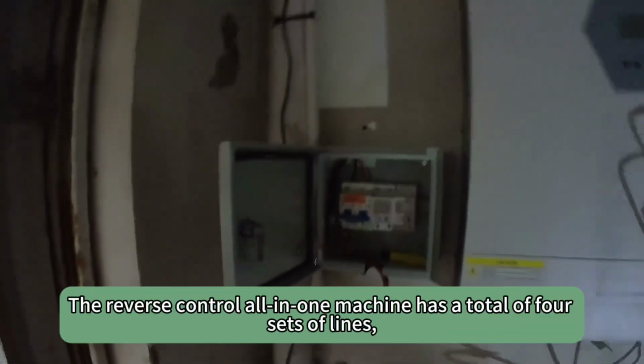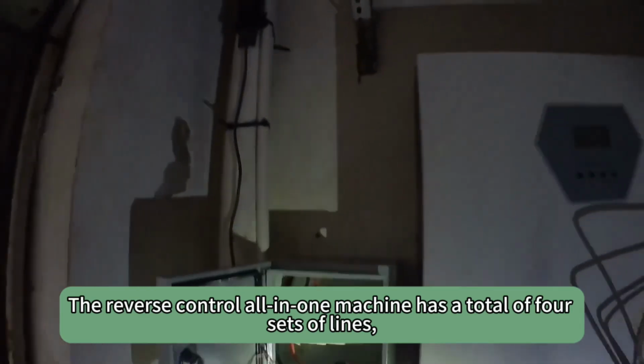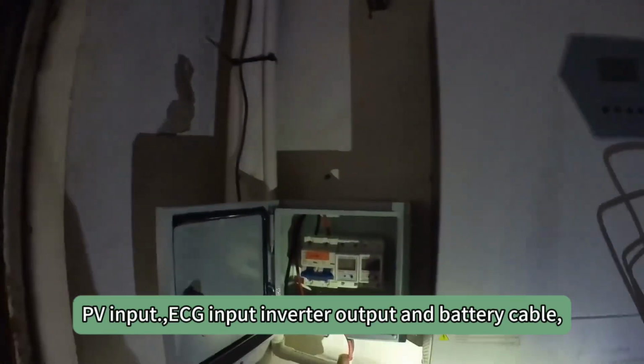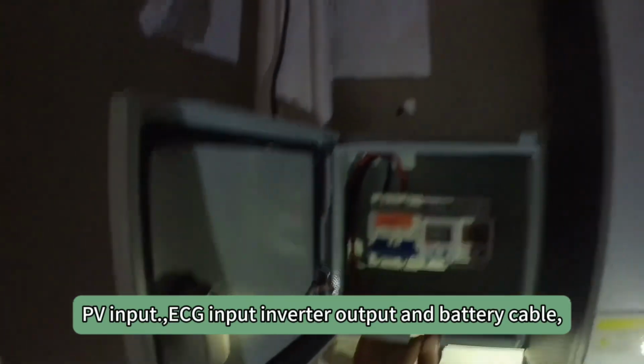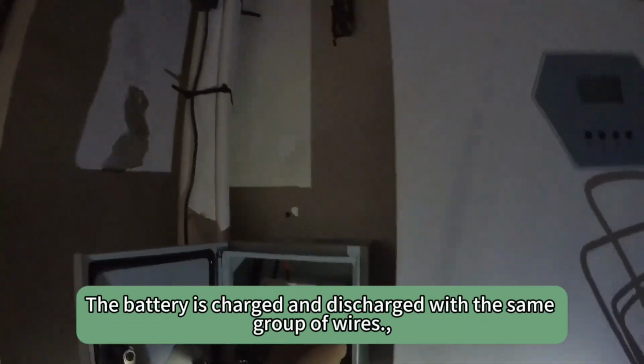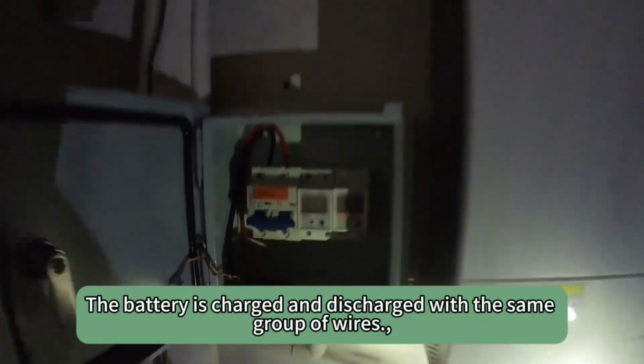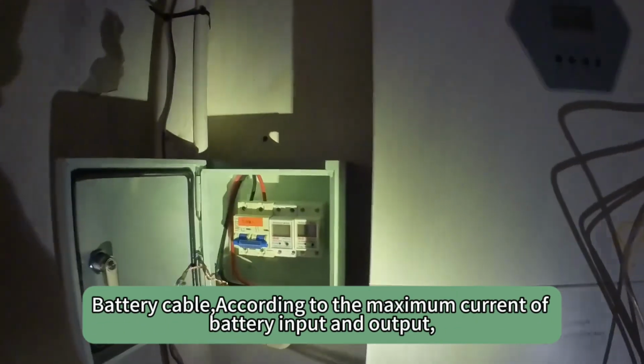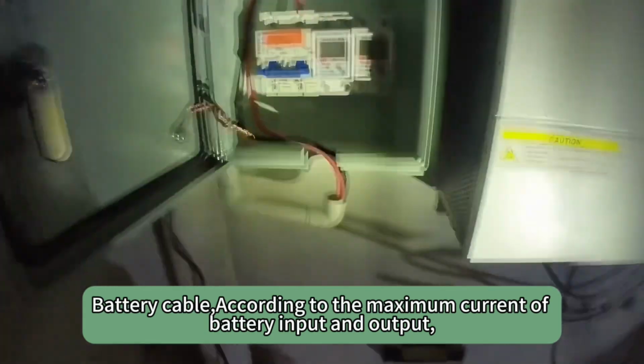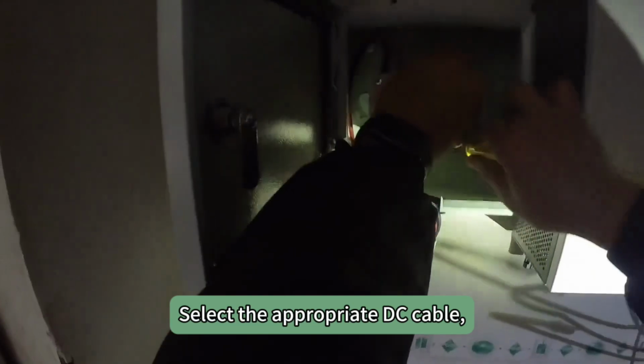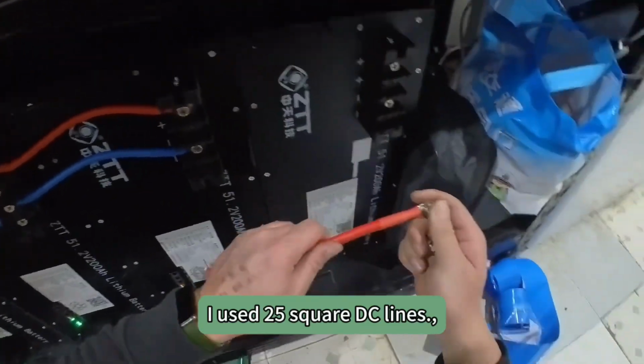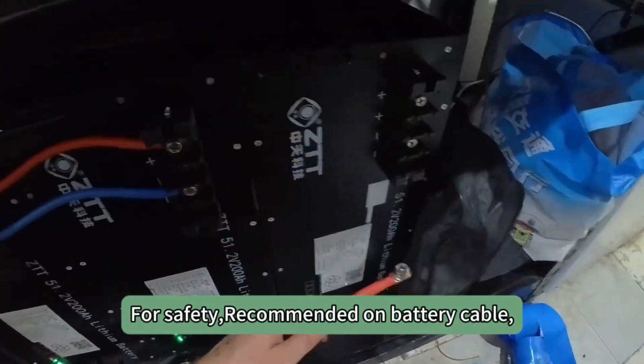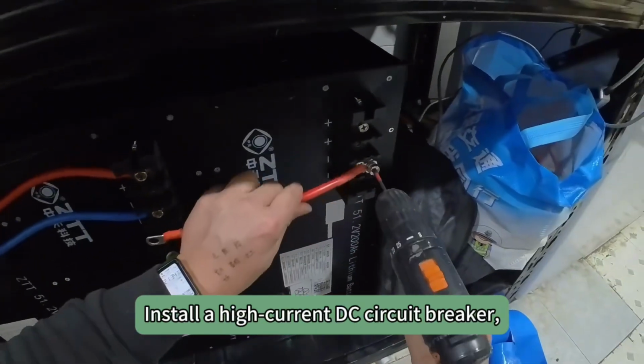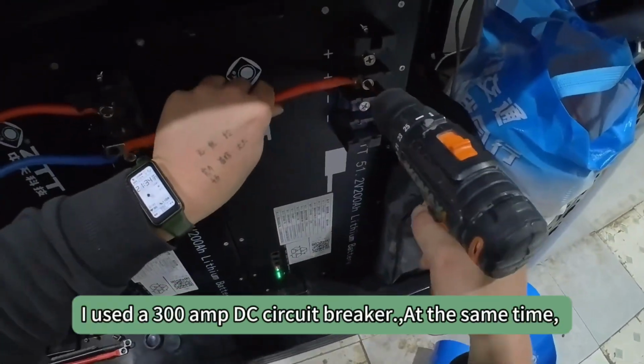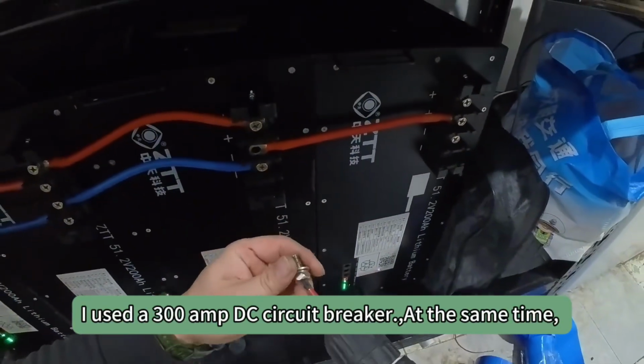The inverter-controller all-in-one machine has a total of 4 sets of lines: PV input, grid input, inverter output, and battery cable. The battery is charged and discharged with the same group of wires. For the battery cable, select the appropriate DC cable according to the maximum current of battery input and output. I use 25 square DC lines. For safety, it is recommended to install a high current DC circuit breaker on the battery cable. I used a 300 amp DC circuit breaker.